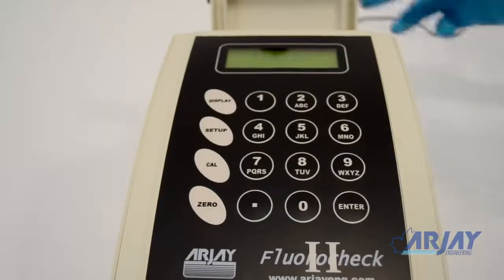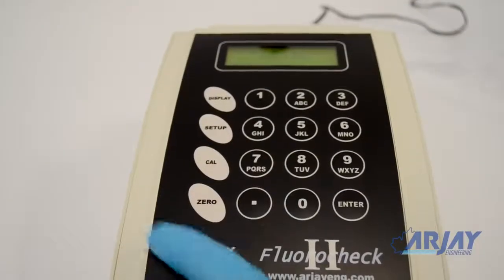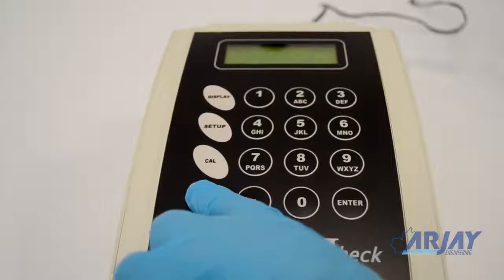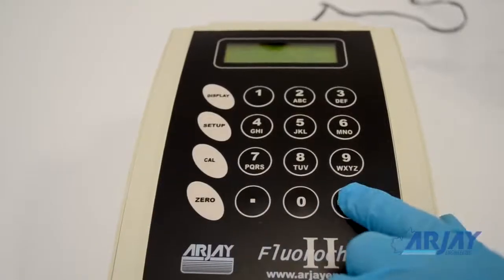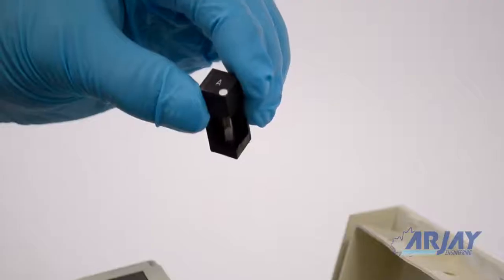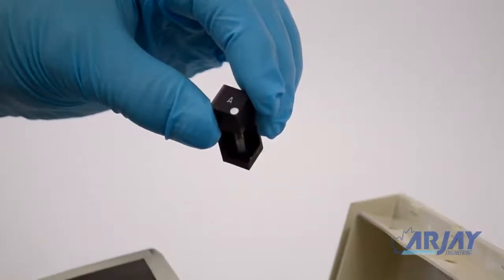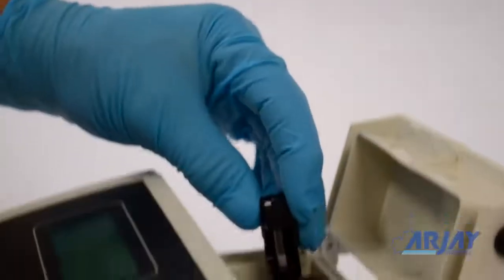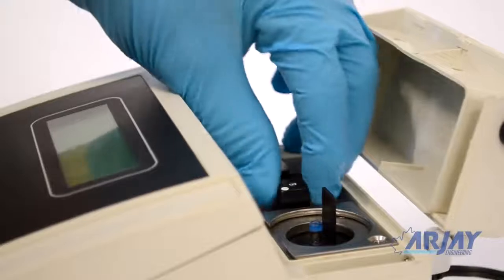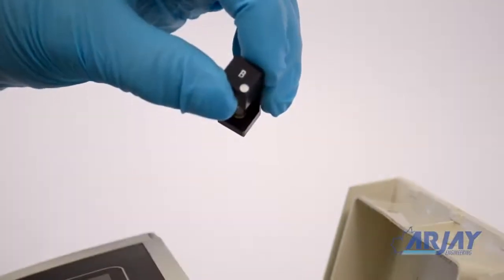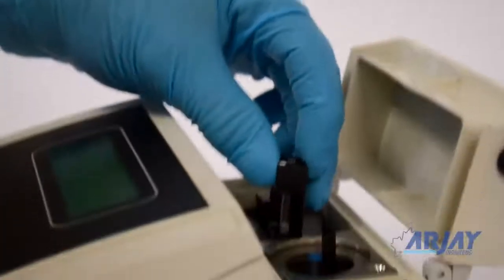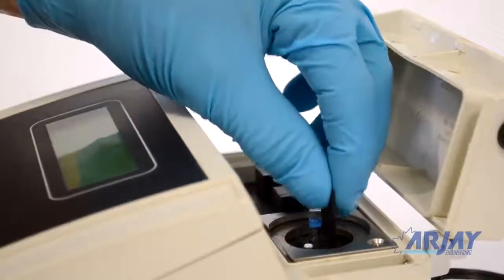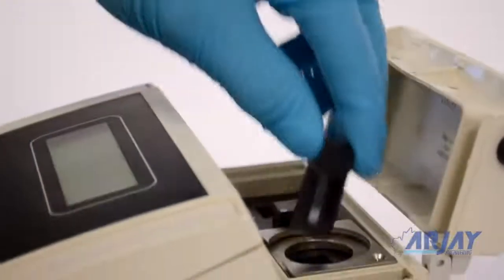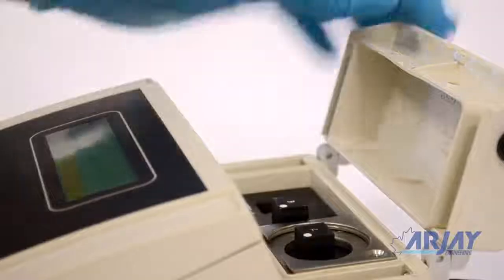A routine 0 is recommended to optimize accuracy. A blank sample is simply put in the unit and the 0 button is pushed. The rest is done automatically. In the sample well, you will find reference standards and a cuvette holder. Reference standard A is used for crude oil applications, and reference standard B is used for refined oil applications. These are assigned a ppm value that is specific to your site application and can be used at any time to check your unit's calibration.